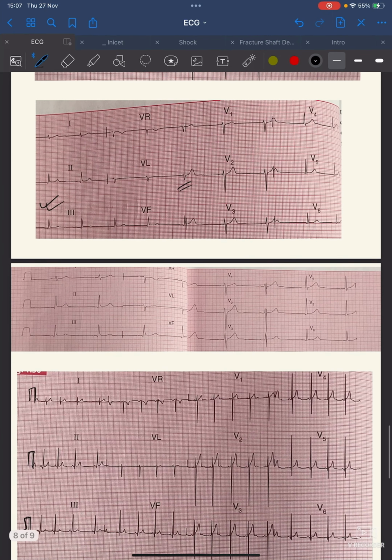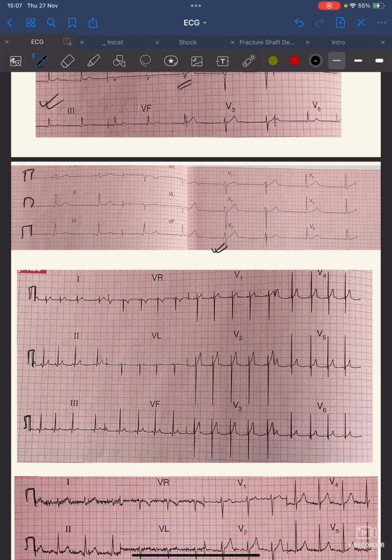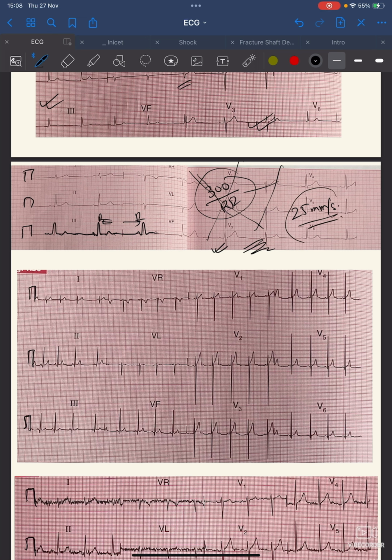So this is the calibration, and if you see here, this has been recorded at a speed of 50 millimeters per second. A paper speed of 50 millimeters per second means it will print 50 millimeters per second. Before, we used to record at 25 millimeters per second. This is 25 millimeters per second, and this is 50 millimeters per second. There will be a long interval between the QRS complexes, which gives the impression of a slow heart. You will see P, then QRST, then again P, QRST, so the RR interval will be longer. So you have to know the formula, because if you apply 300 divided by the RR interval here, that will be very wrong, since that concept is used only if the print speed is 25 millimeters per second.